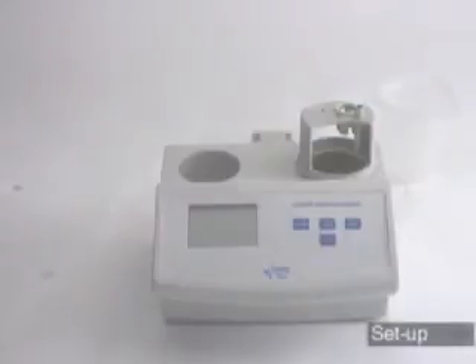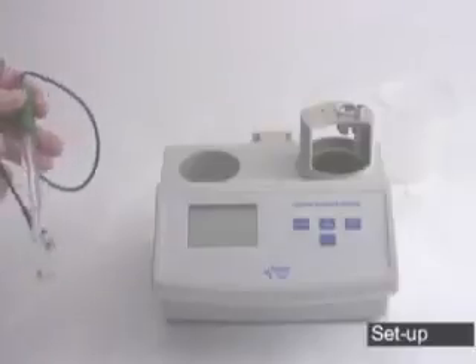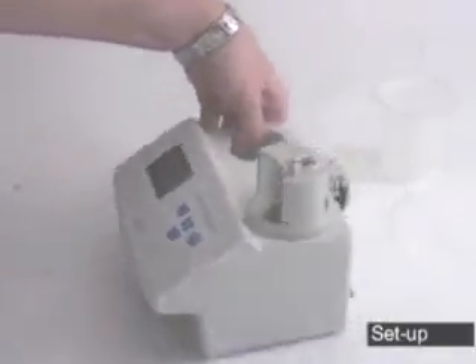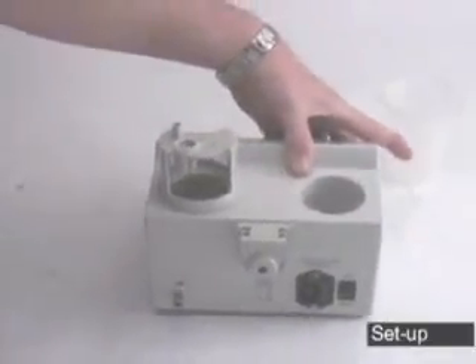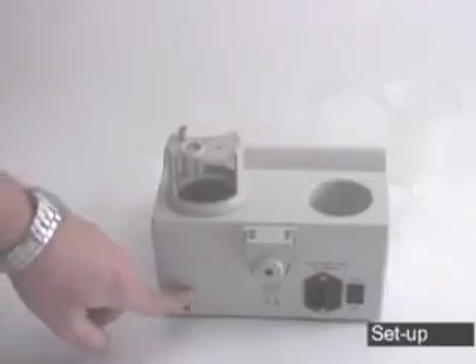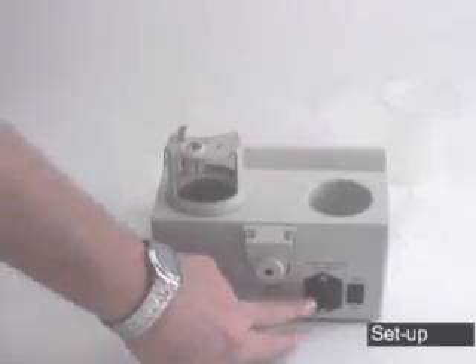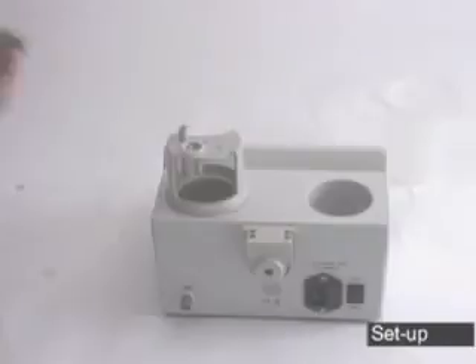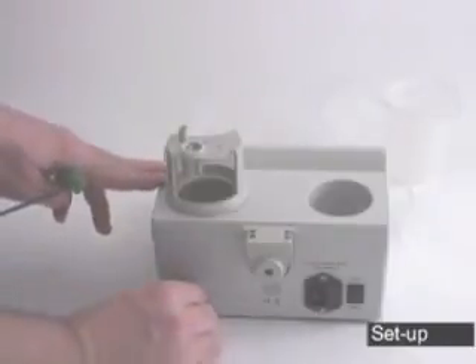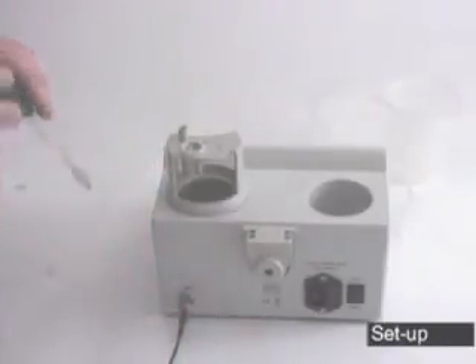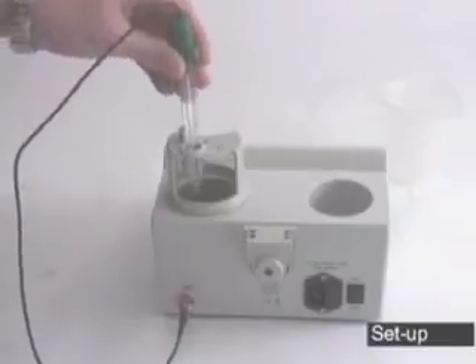Once you have the meter unpacked, first thing we're going to do is hook up the probes and the tubing. Take your probe, remove the cap. In the back of the unit, we're going to have the probe hook up right here, ORP probe, power here, on-off switch. Take the BNC connector, place it over half a turn to lock it into place, put it in the ring provided on the cap.